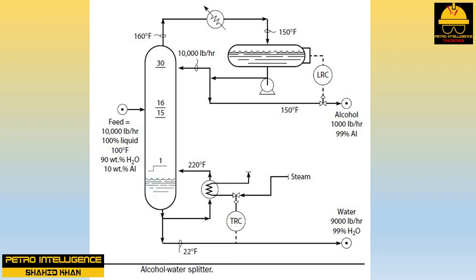There are two ways to answer this question. Let's first look at the reboiler. As the tower top temperature goes down, more of the lighter, lower boiling point alcohol is refluxed down the tower. The tower bottom temperature begins to drop, and the steam flow to the reboiler is automatically increased by the action of the temperature recorder controller (TRC).